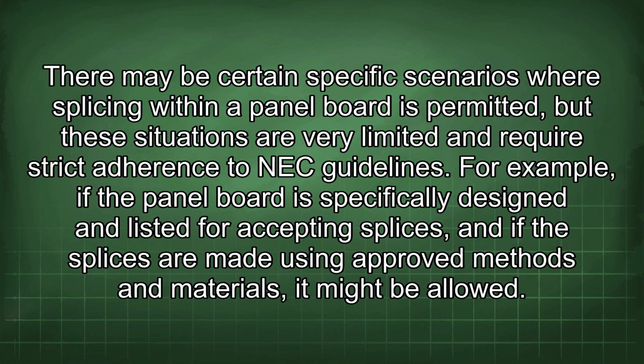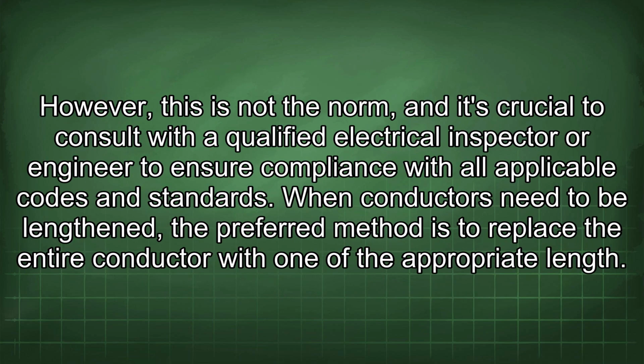There may be certain specific scenarios where splicing within a panel board is permitted, but these situations are very limited and require strict adherence to NEC guidelines. For example, if the panel board is specifically designed and listed for accepting splices, and if the splices are made using approved methods and materials, it might be allowed. However, this is not the norm, and it's crucial to consult with a qualified electrical inspector or engineer to ensure compliance with all applicable codes and standards.